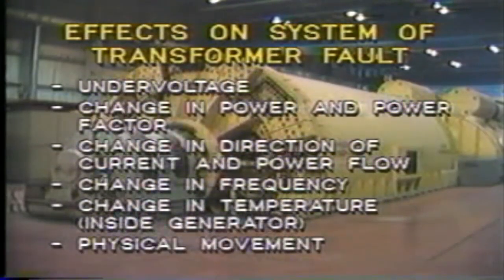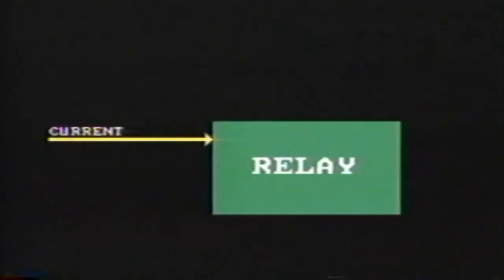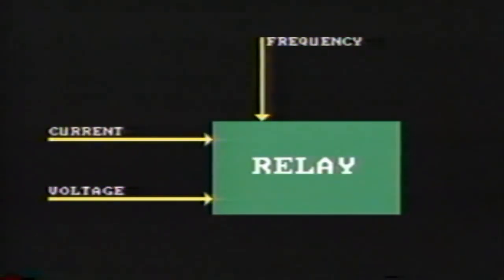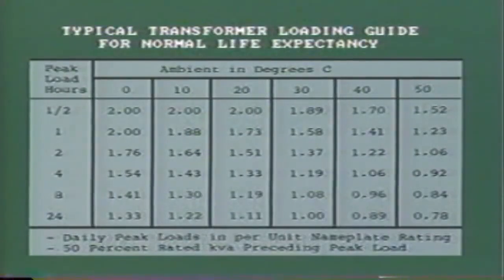physical movement, for example, the generator windings. I'm sure you can think of others, and it's these very changing conditions which allow the relays to sense and detect the presence of a fault. Most relays use one, but often several of these changing factors, sometimes called handles, to determine whether the fault condition is acceptable or not. We must recognize that some fault conditions may be tolerable, at least for a short period of time, but others may be intolerable and require immediate isolation from the system to prevent damage.